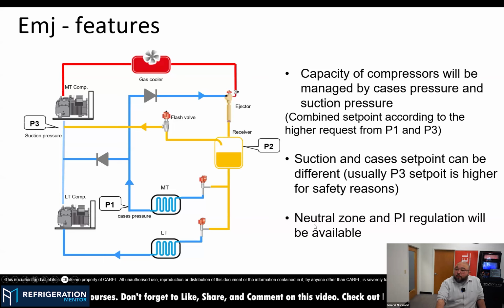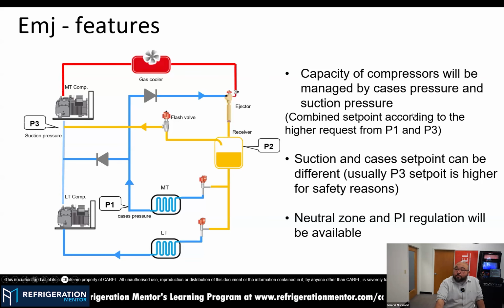Normally what we do is we control these compressors with two different types of logic: neutral zone when I have more than one compressor, to avoid cycling of the compressors, and PI when I have only one variable speed compressor, to adjust the capacity and make it as precise as possible.